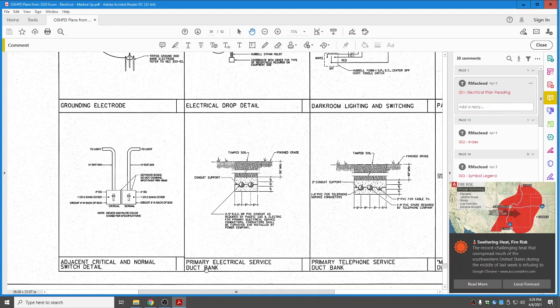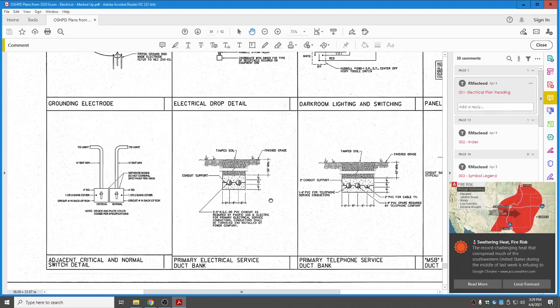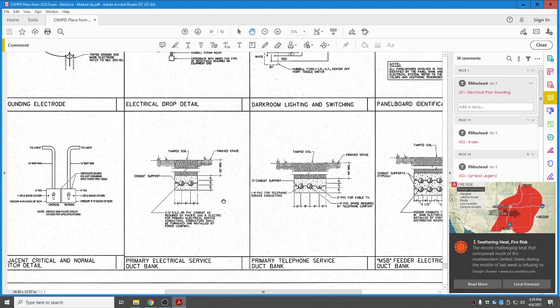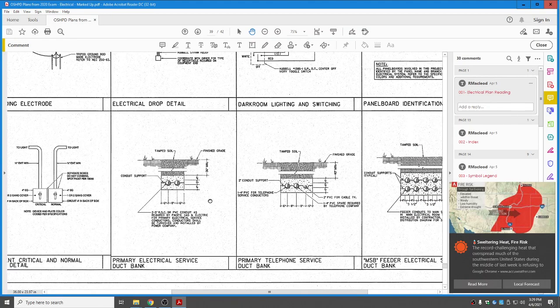And here's some duct banks. These are buried items encased in concrete. This particular one is showing primary electrical service into the building, depth of burial, the thickness of the concrete around it, the spacing between the conduits. Next one is a primary telephone service duct bank, once again also encased in concrete with a different burial depth.